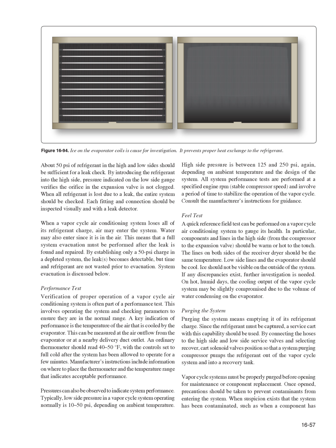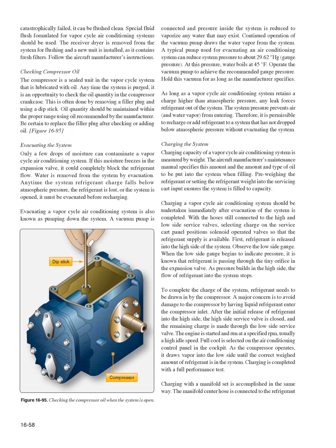When suspicion exists that the system has been contaminated, such as when a component has catastrophically failed, it can be flushed clean. Special fluid flush formulated for vapor cycle air conditioning systems should be used. The receiver dryer is removed from the system for flushing and a new unit is installed, as it contains fresh filters. Follow the aircraft manufacturer's instructions. Checking compressor oil. The compressor is a sealed unit in the vapor cycle system that is lubricated with oil.